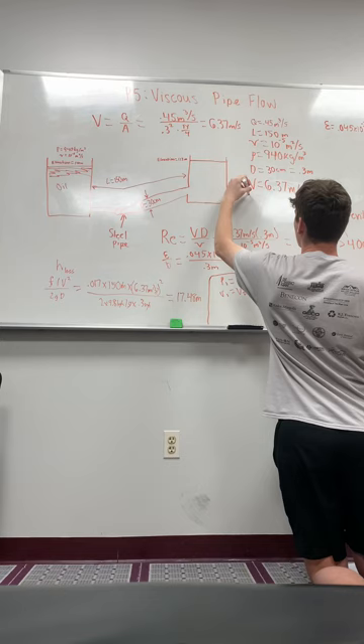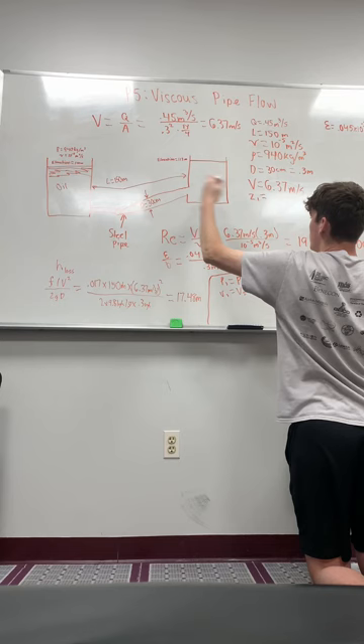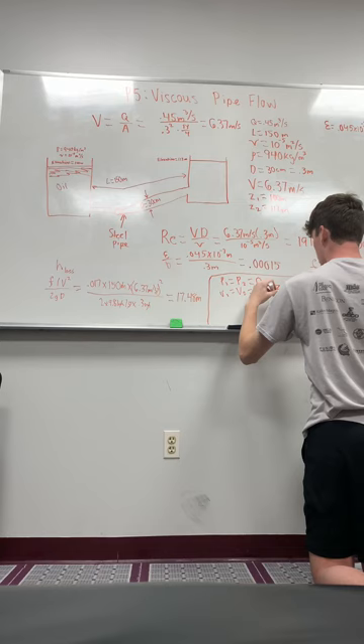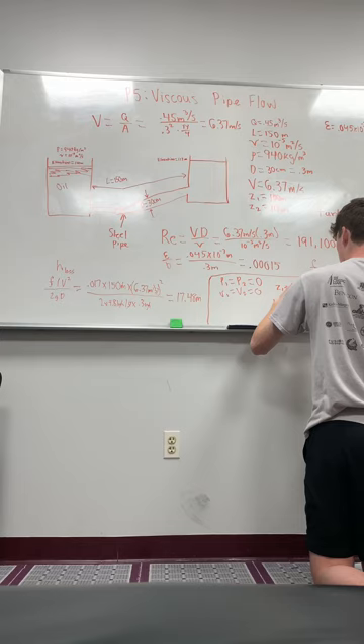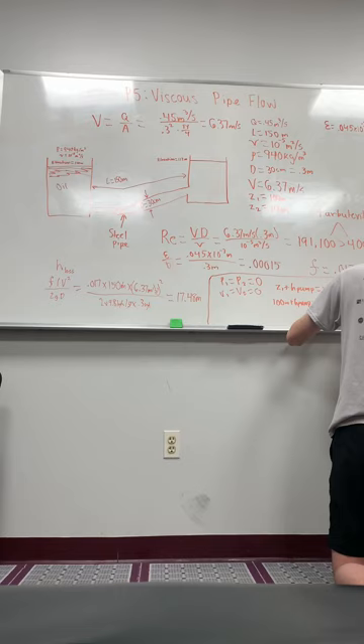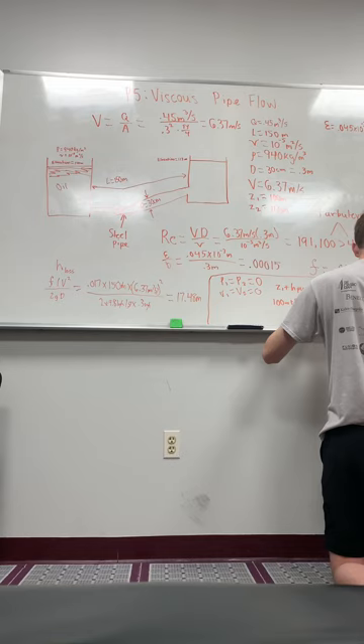So the Z1 is equal to the elevation of the bottom tank, so 100 meters. And Z2 is equal to 112, which is the elevation of the second tank. So it'd be 100 meters plus pump head equals 112 meters plus 17.48 we just got. That would give us the pump head would be 29.48 meters.